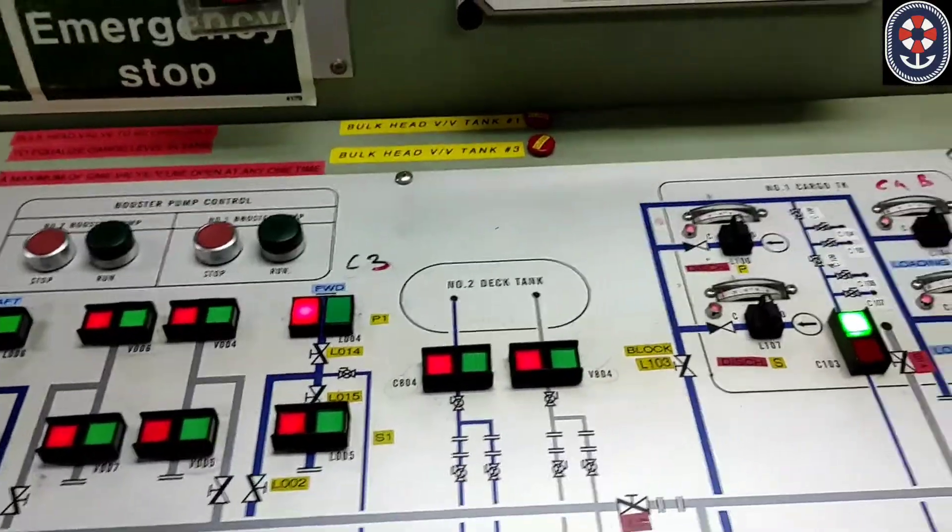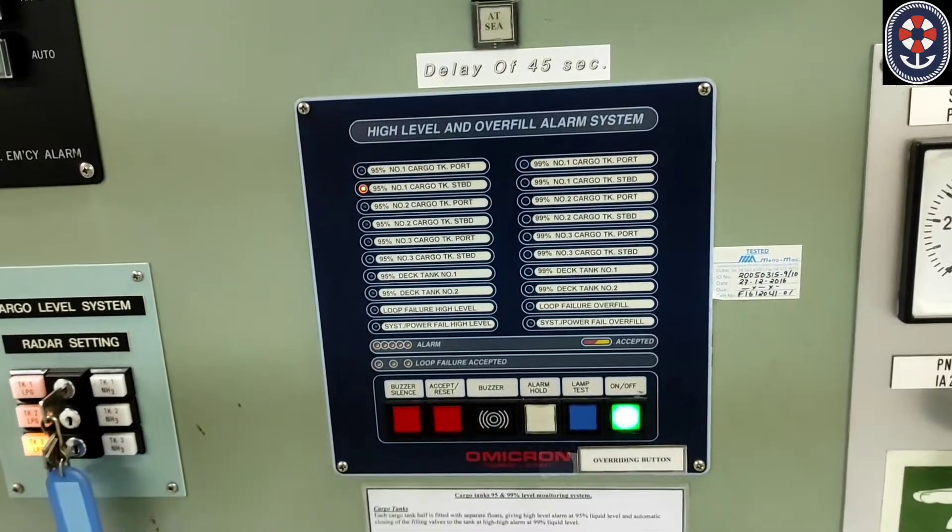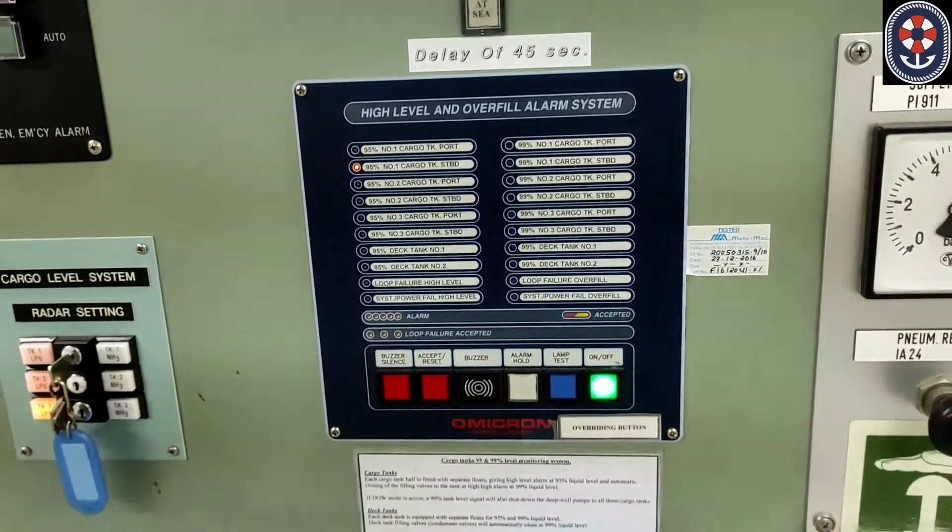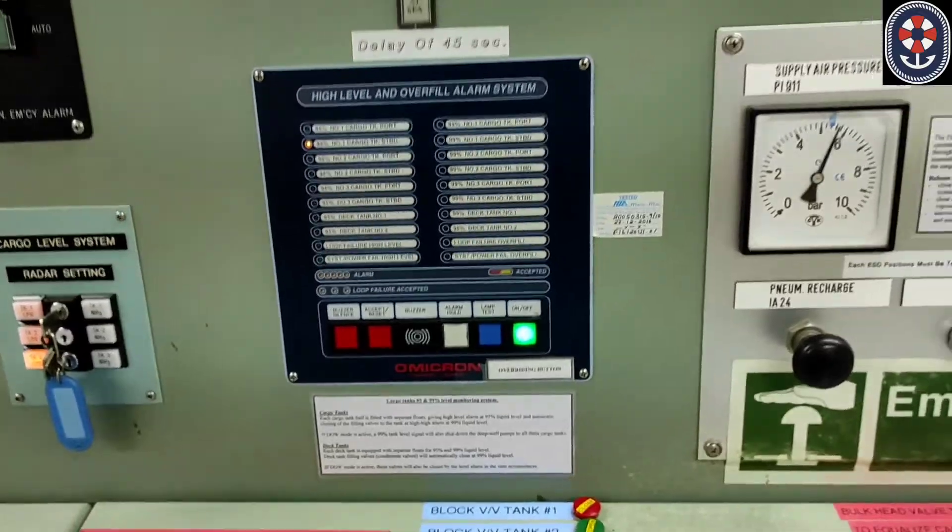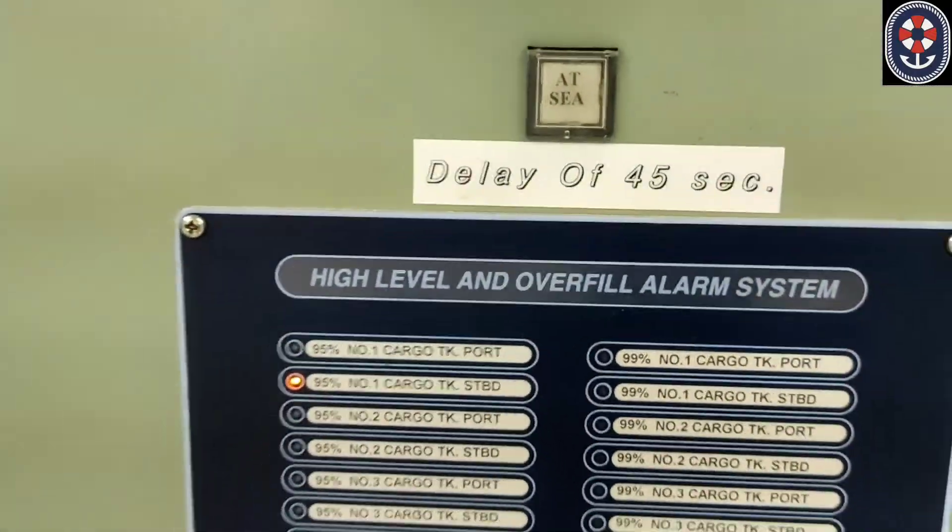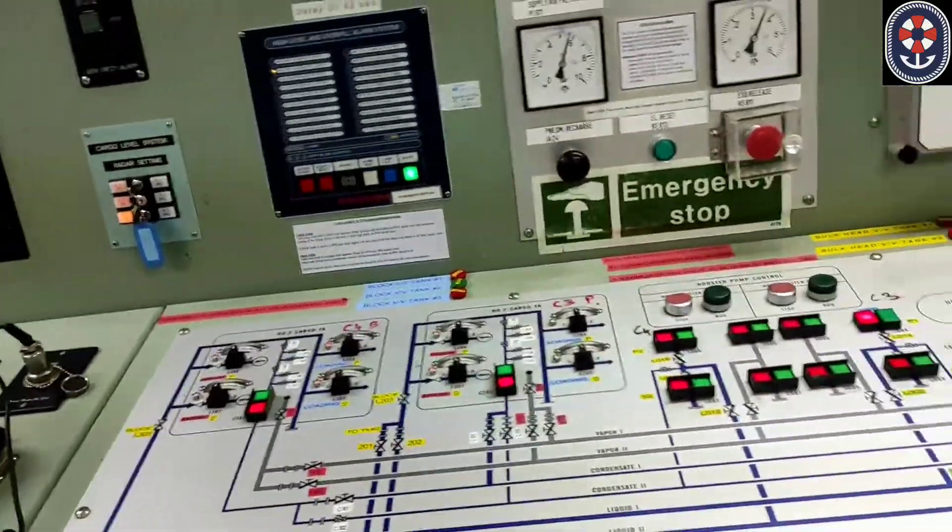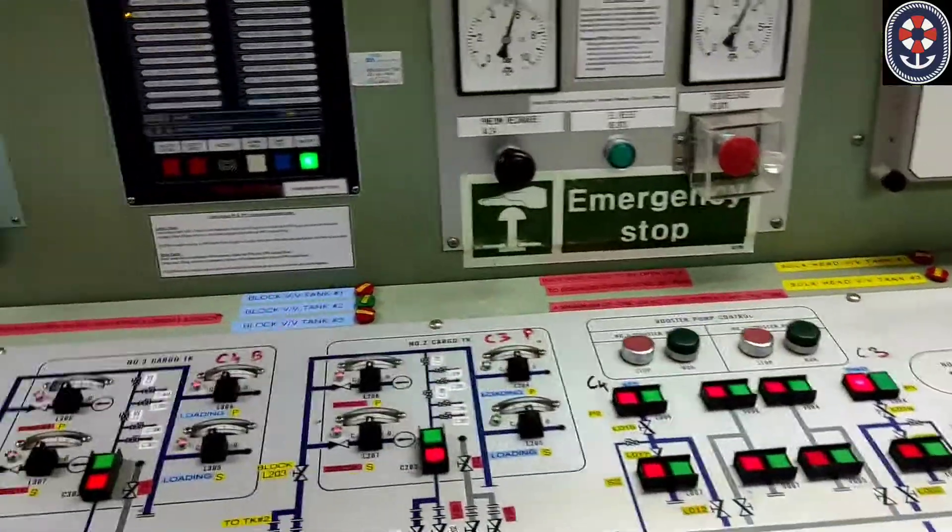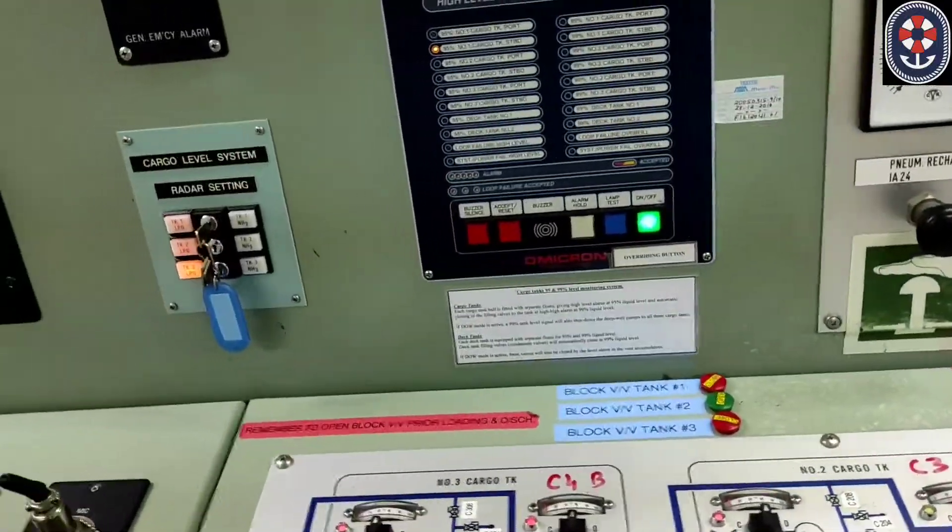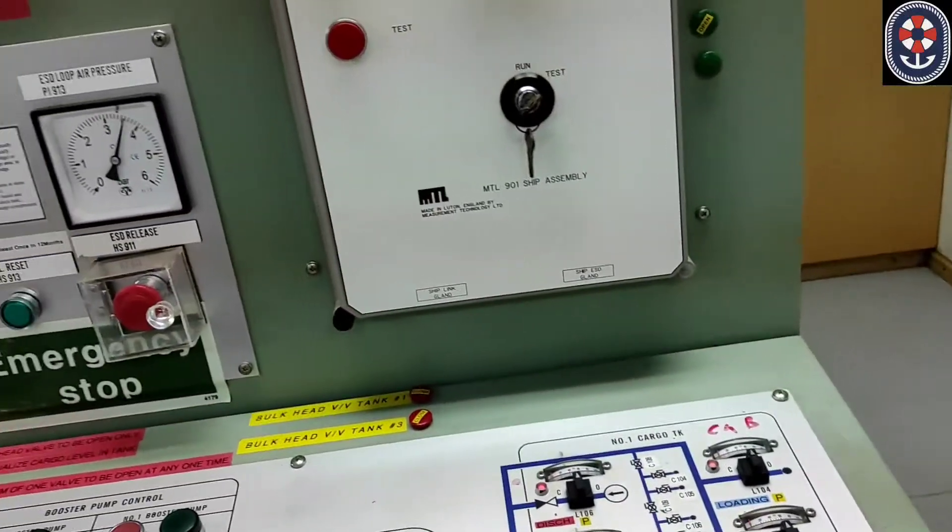And then you can find here for tank level gauge: 99 percent, 98 percent alarm, and this is the setting. Then we have also a setting here. At sea, when you switch it to at sea, it will give alarm after there is a delay of 45 seconds. When you are at sea, so that during rolling, it will not give this much alarms. And if you go further, we can see emergency test shutdown system.